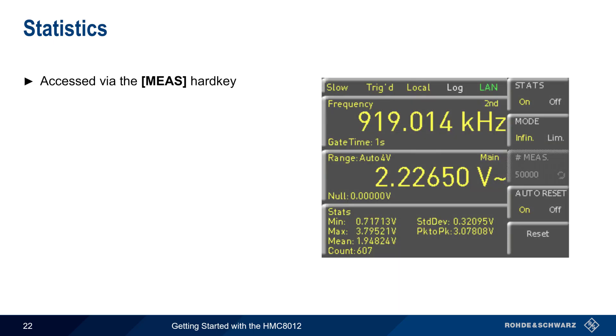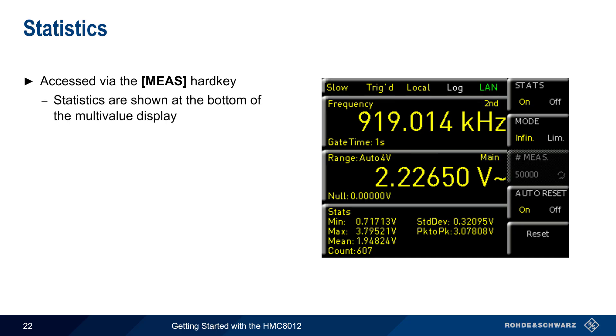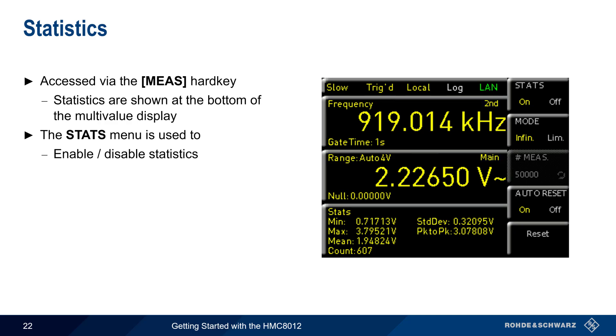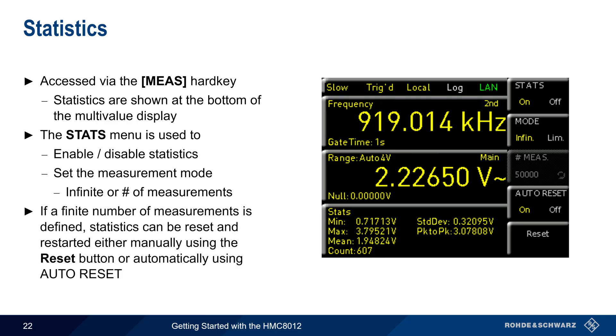Statistics on the HMC 8012 are enabled and configured using the measure hard key, and when enabled, statistics are shown in the bottom portion of the multi-value display. The stats menu is used to both enable and disable statistics, as well as to set the measurement mode – either infinite, or for a user-defined number of measurements. If a finite number of measurements is specified, statistics can be reset and restarted either manually using the reset key, or automatically by enabling auto reset.